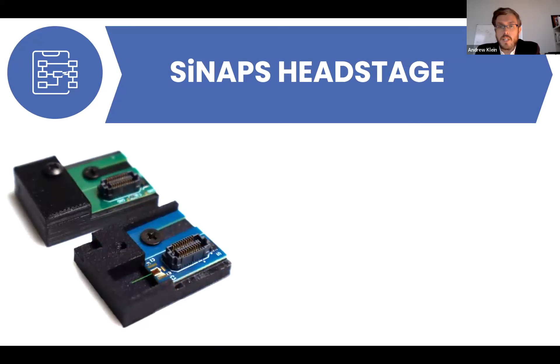Starting from the left, let's talk about the new head stage developed by Plexon for use with SiNAPS probes. The SiNAPS head stage is a Plexon developed piece of hardware that marries the probe to an interface accessible by the OmniPlex system. In the image are two SiNAPS head stages, one blue and one green, within a black 3D printed protective case. The probe can be seen in the foreground of the blue head stage. Here is a zoomed in version.